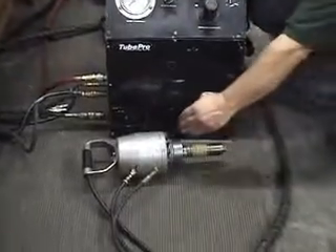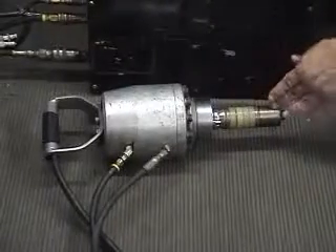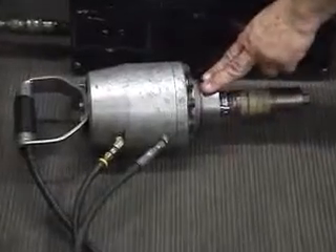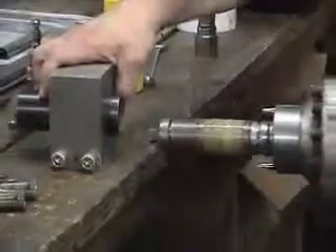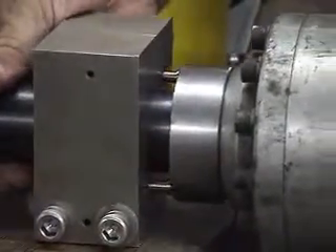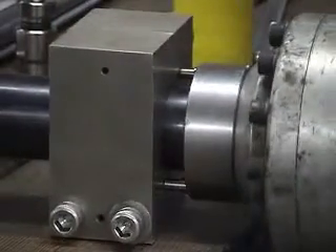It is basically a pull cylinder on a mandrel shaft, which in this case is called a drawbar, with a reactionary anvil and wear ring. You insert the TubePro and engage the pins all the way to the tube sheet.